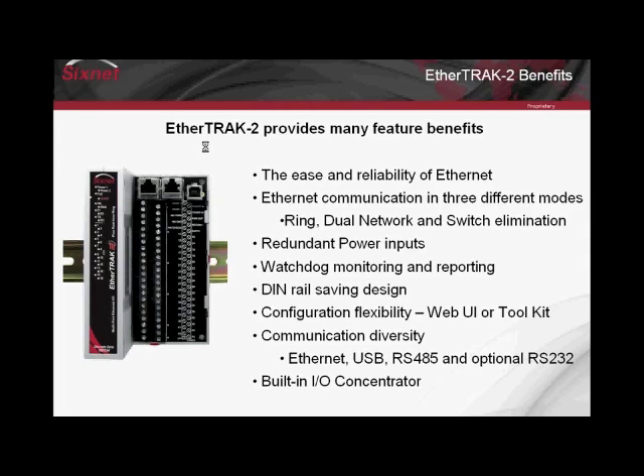Dual Ethernet ports have three different jumper-selectable modes. Ring mode uses the 6Net ring protocol for fast recovery on Ethernet failure. Network mode allows each Ethernet port to be on a separate Ethernet network with differing subnet masks. Switch elimination mode allows daisy-chaining multiple modules without the use of another switch. There are also redundant 10 to 30 volt DC inputs.